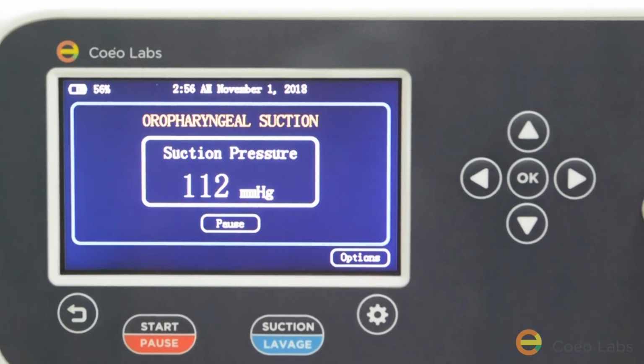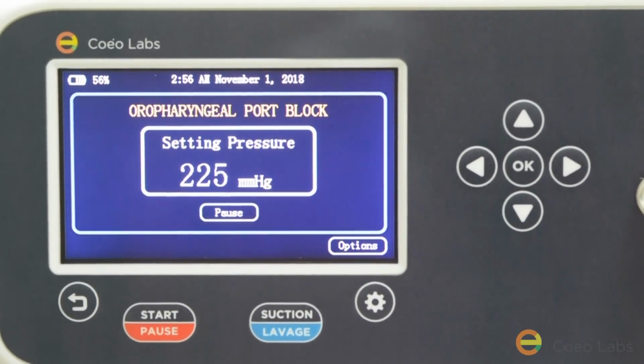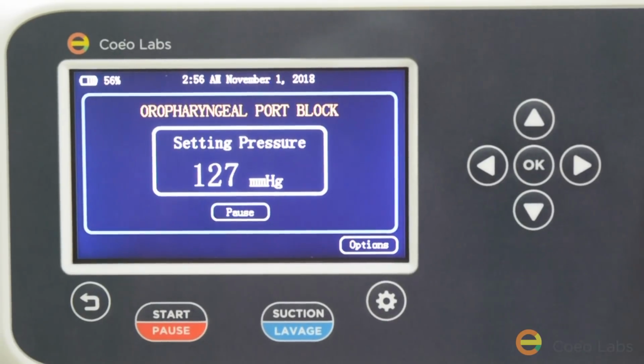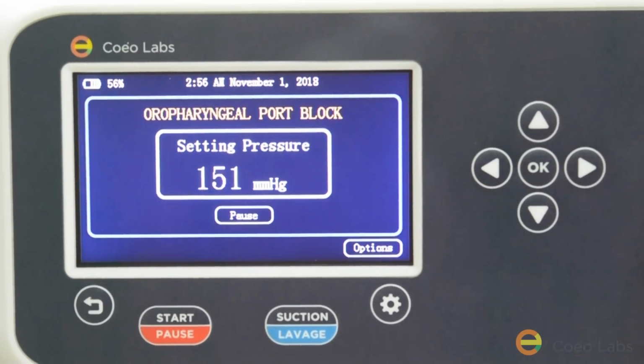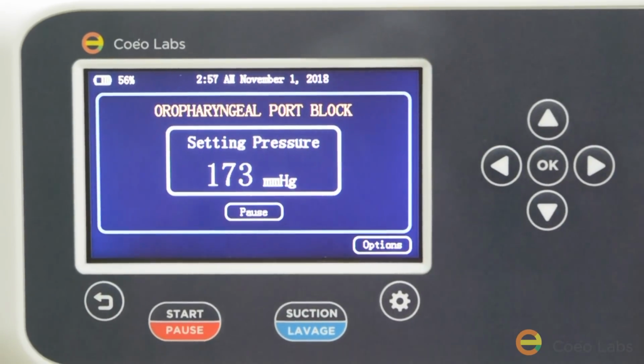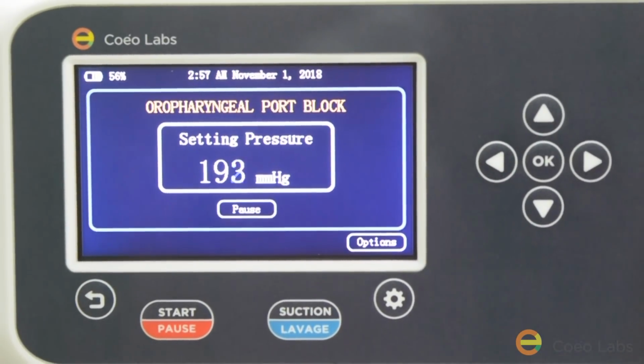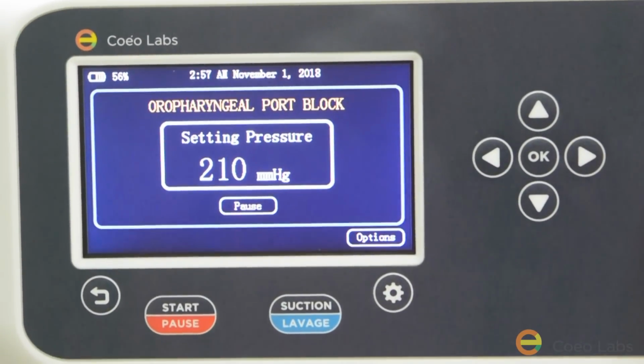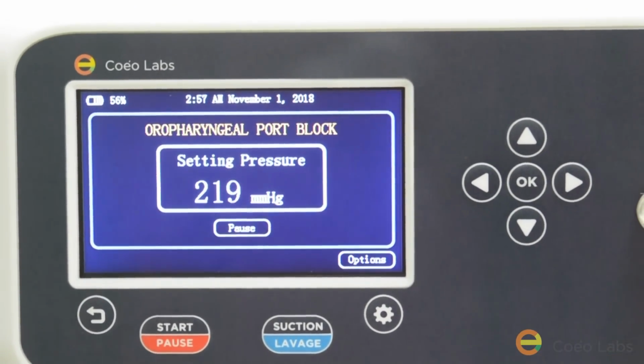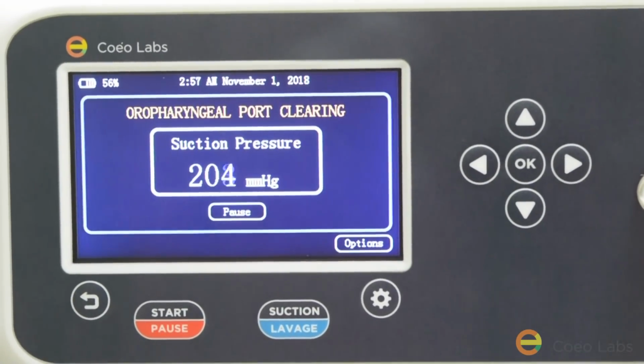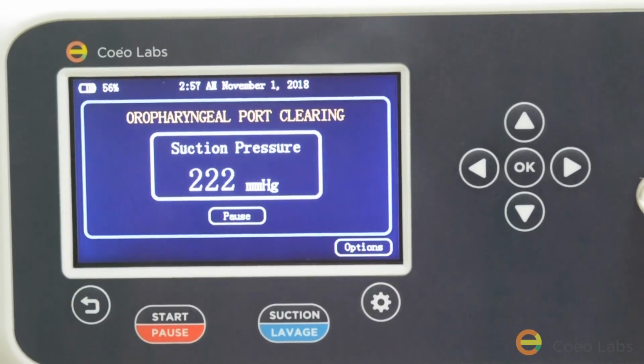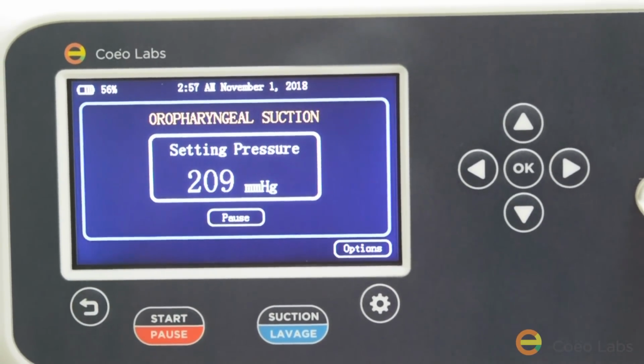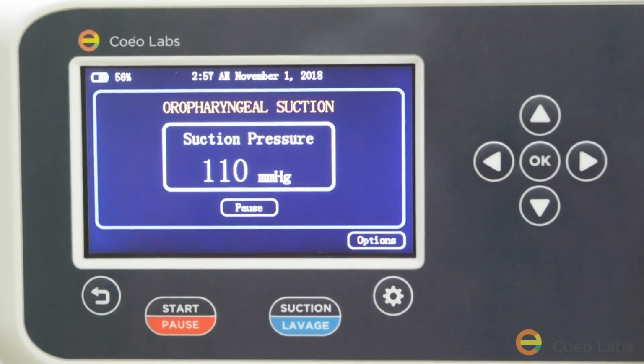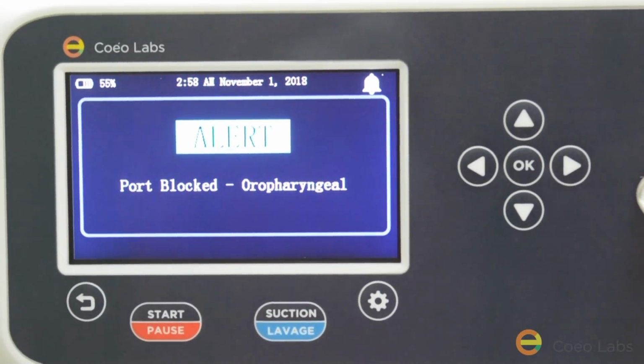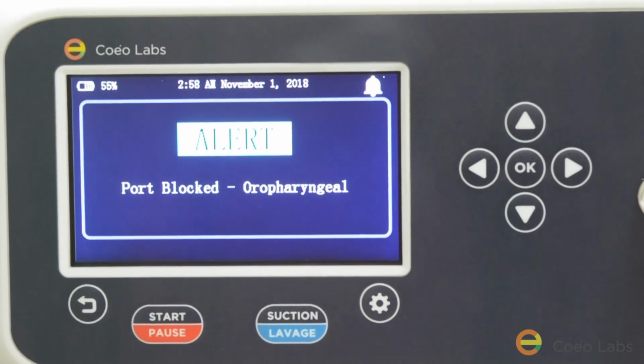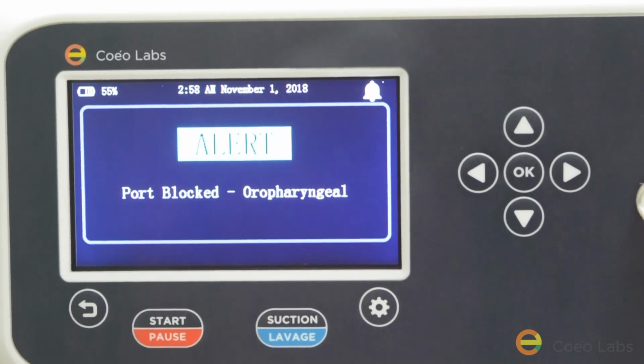In case of port block detection, the device raises the pressure transiently to the port unblocking pressure of 225, which can be set anywhere from 45 to 285 millimeters of mercury. The device attempts to relieve the port block for 3 consecutive attempts, and in case of failure, it throws an alert on the screen for manual intervention. To demonstrate the port block, we have simulated it, and this is the third port block going on. This is the alert. It's an oropharyngeal port is blocked. So this actually requires a manual intervention.